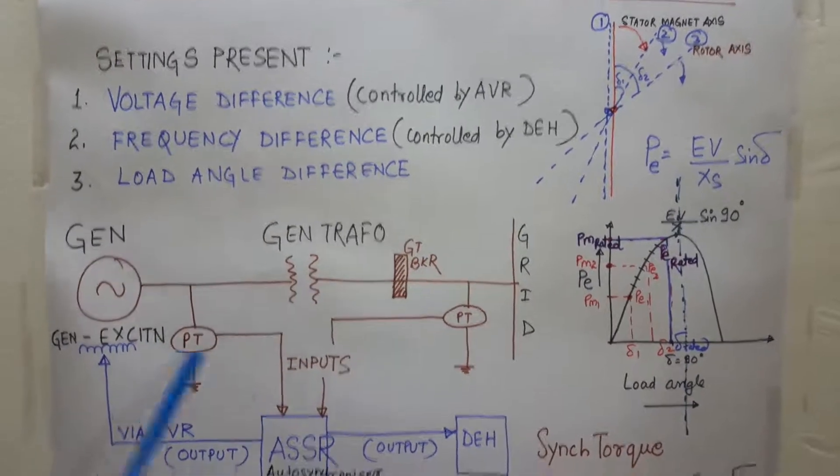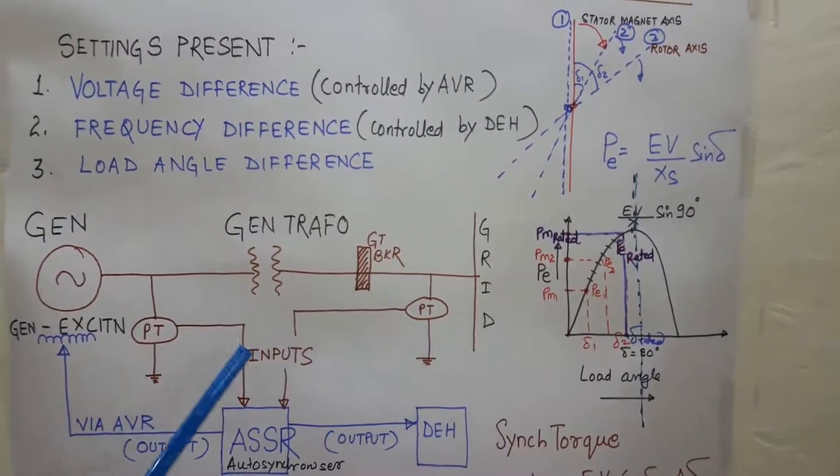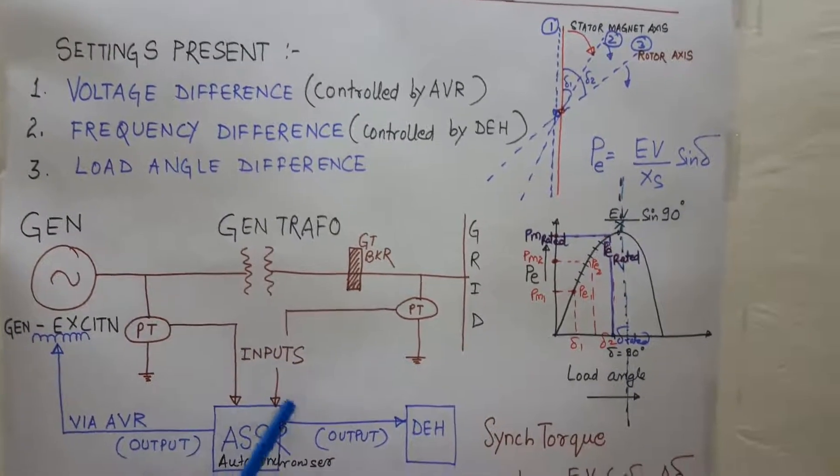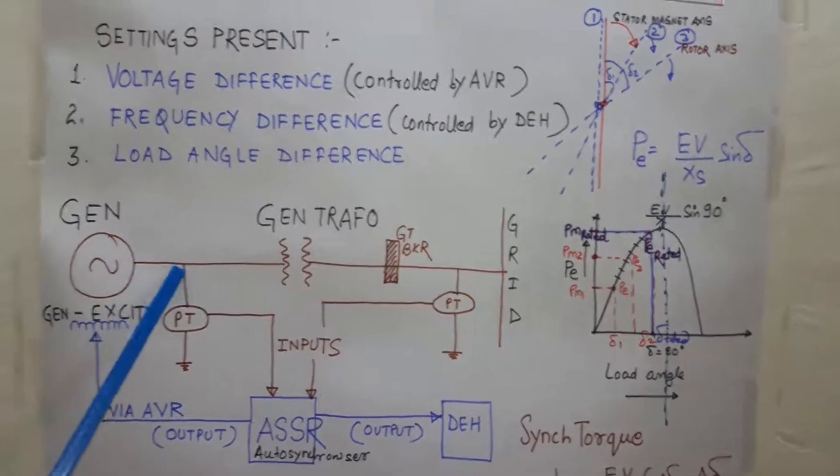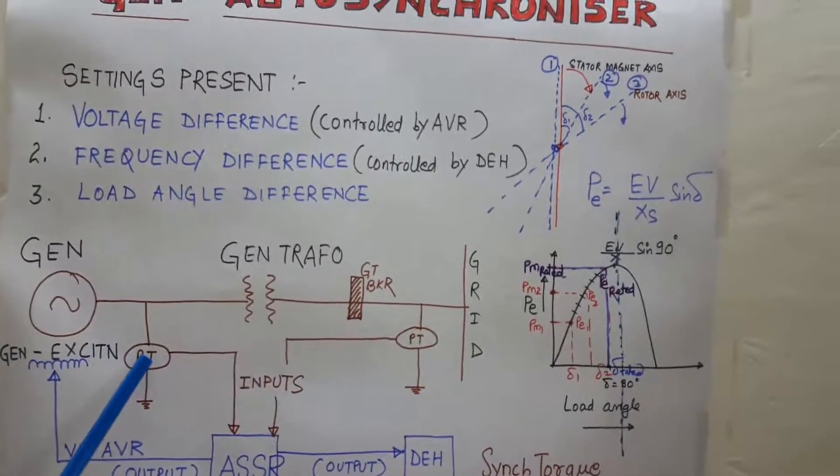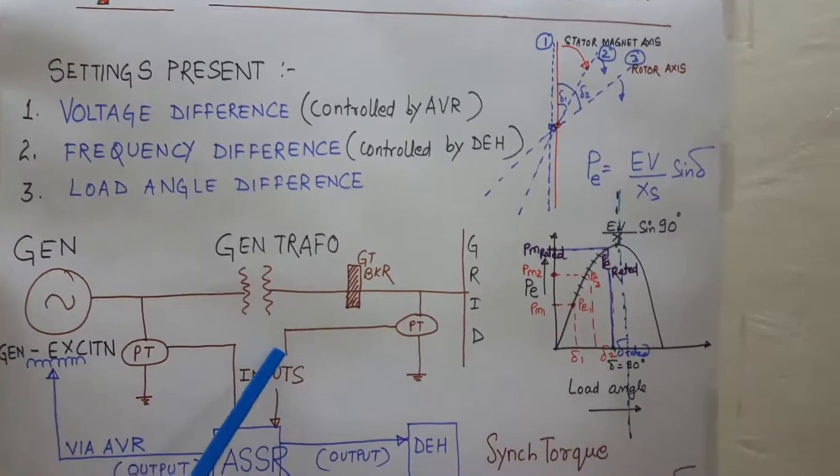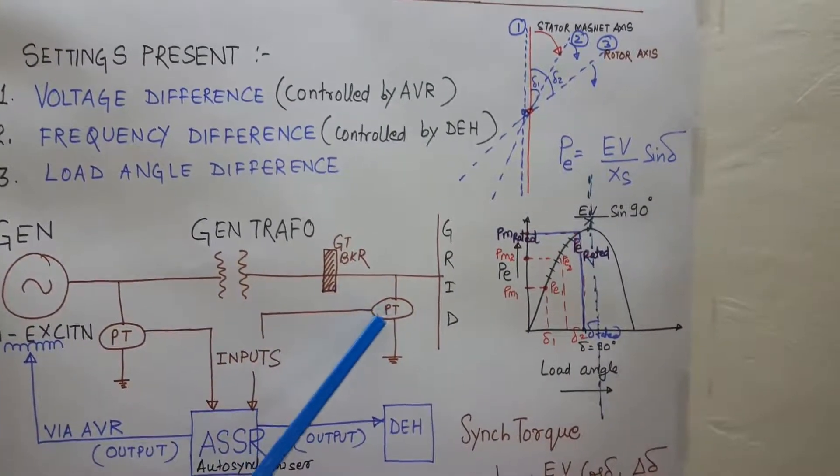These are the two potential transformers which are giving inputs to the device called auto synchronizer. One input is coming from the generator PT for measuring the generator terminal voltage. Another input is coming from the switchyard bus PT for measuring the voltage of the grid or infinite bus.